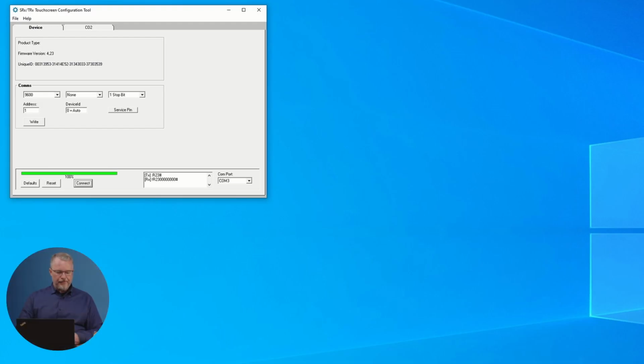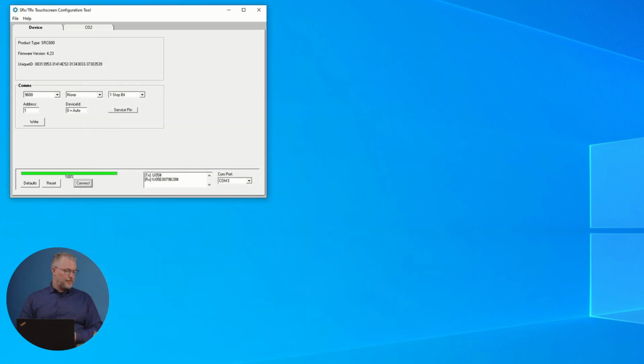Now I go back to my USB tool software. And I go to the file. And now I want to store the parameters first. Oh, okay. I press the save. Now the software reads all the data inside the device. So all the things and settings that I have done here go through the small cable to your computer. Yes. And there we will be able to store it. Very fancy. I will call this file TRC configuration. Okay. Now it's stored on my computer.